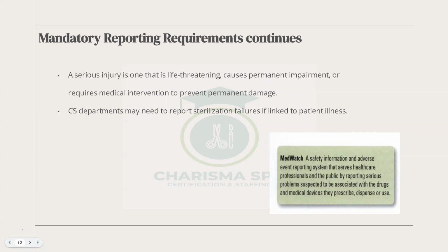Biologicals are classified as class 2, which falls under our department. If for any reason it fails, you sterilize, you expose it to temperature, humidity, and time, and the biological turns positive, then we need to report to the manufacturer. The whole pack is turning from negative to positive.